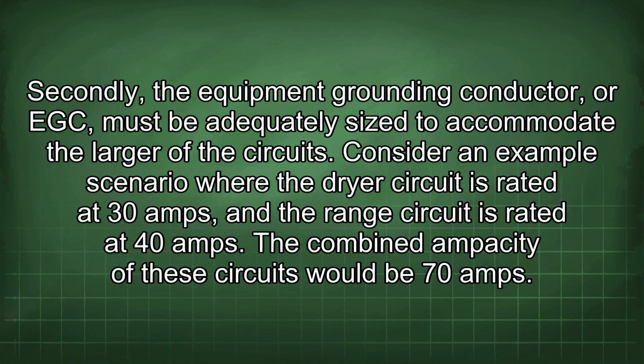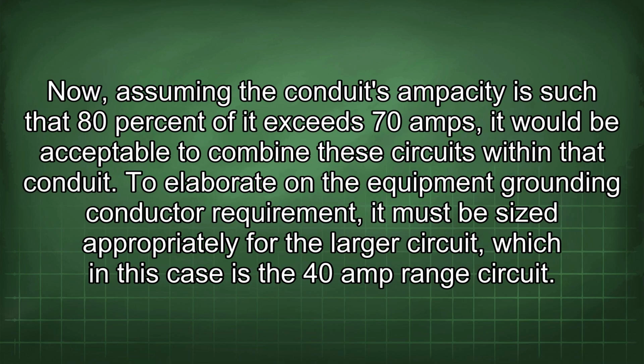Consider an example scenario where the dryer circuit is rated at 30 amps and the range circuit is rated at 40 amps. The combined ampacity of these circuits would be 70 amps. Now, assuming the conduit's ampacity is such that 80% of it exceeds 70 amps, it would be acceptable to combine these circuits within the conduit. To elaborate on the equipment grounding conductor requirement, it must be sized appropriately for the larger circuit, which in this case is the 40 amp range circuit.